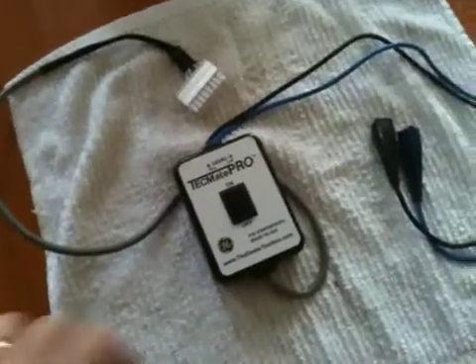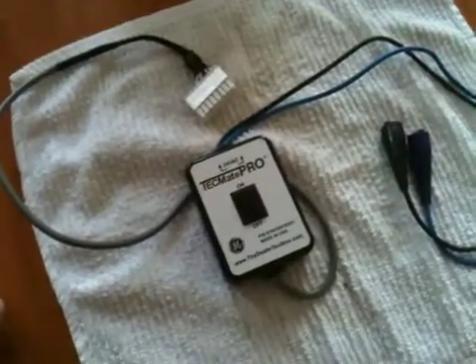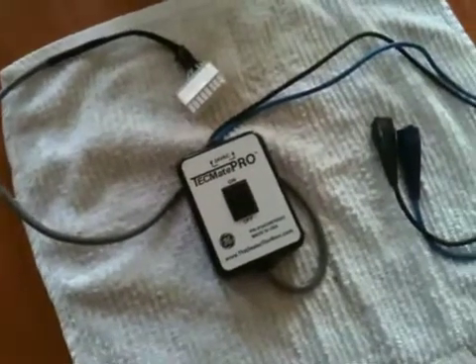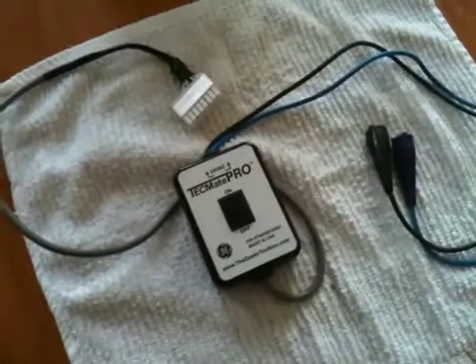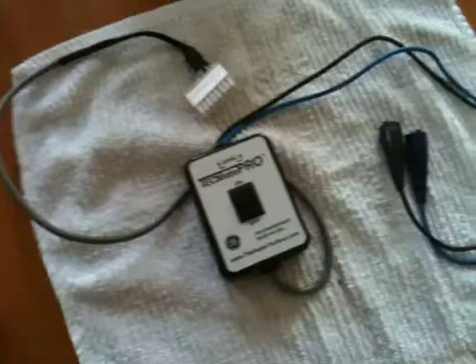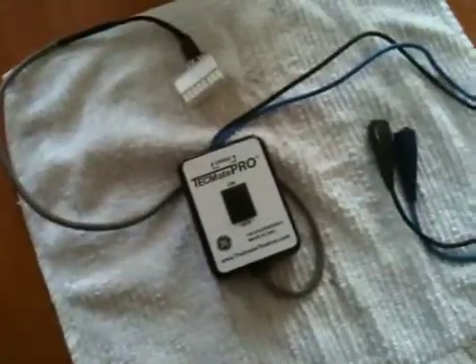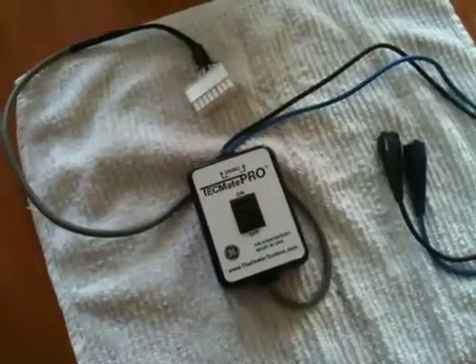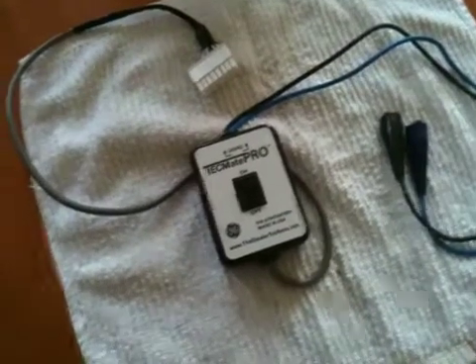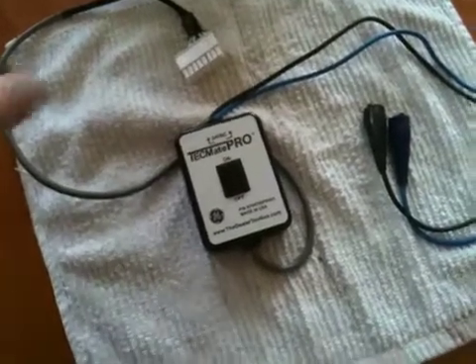Maybe we'll get some other guys to pipe in here if they have test equipment that will test the motor or the module. There's a pretty good consensus that everyone says 89% of the time it's the module that goes out, not the motor. But I haven't actually looked for a piece of equipment that can differentiate between the two, so maybe someone else out there has a method or a piece of equipment that will do that.